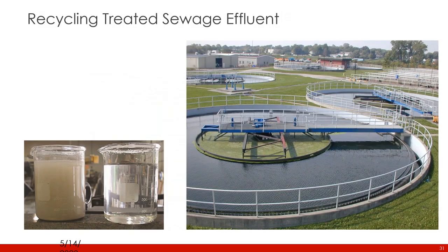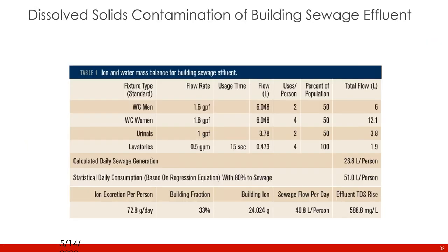So when we talk about recycling treated sewage effluent, basically here we have our sewage water, and here we have our treated sewage water. And this is a large typical sewage treatment plant. The problem, however, is that typical sewage treatment plants do not deal with dissolved solids. Dissolved solids are inorganic salts of various kinds. So standard treatment plants utilize bacteria basically to get rid of all the organic contaminants, but they don't do anything typically about the inorganic contaminants.